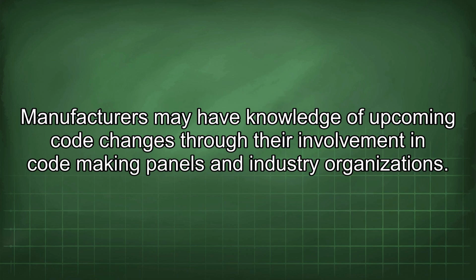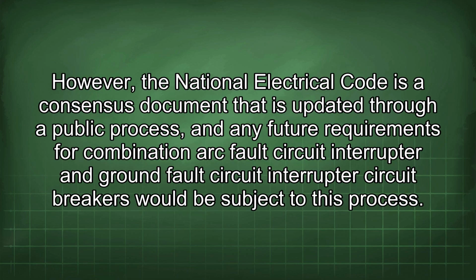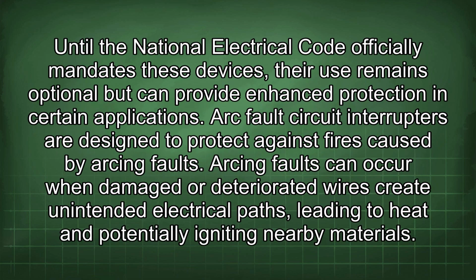Manufacturers may have knowledge of upcoming code changes through their involvement in code-making panels and industry organizations. However, the National Electrical Code is a consensus document that is updated through a public process, and any future requirements for combination arc fault circuit interrupter and ground fault circuit interrupter circuit breakers would be subject to this process. Until the National Electrical Code officially mandates these devices, their use remains optional but can provide enhanced protection in certain applications.